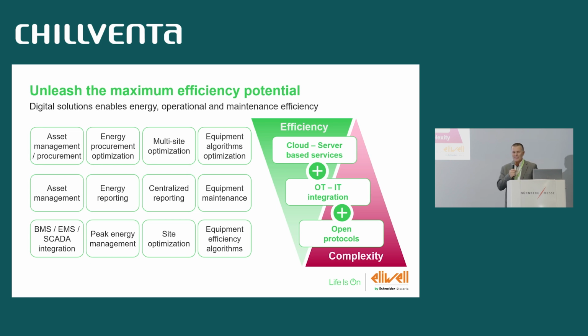I'll mention some of the potential at various levels in terms of efficiency. It's not typically just switching off loads to consume less, or reducing loads by using modulation - something we do in the machine typically. It's also something we can do with modulation based on an entire system. For example, in our system you may have floating suction control in a compressor rack based on the loads. So having integration between the loads and the compressor rack at the system, at the refrigeration system level, is a way to achieve a certain level of efficiency.